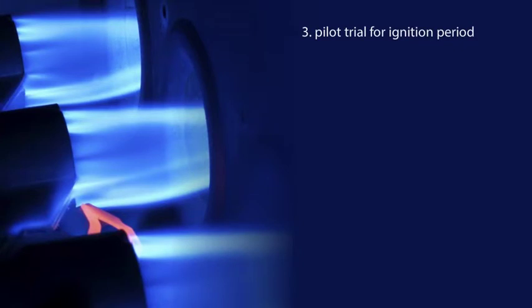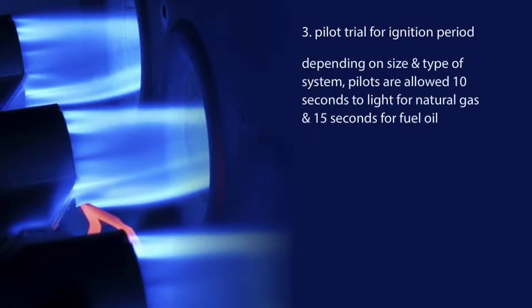The pilot trial for ignition period. Depending on the size and type of system, pilots are allowed 10 seconds to light for natural gas and 15 seconds for fuel oil. This is often a configurable setting on modern BMSs, although in the case of some equipment, it's a permanent change. You can always decrease it, but you cannot increase it when configuring on most BMS systems. It should also be noted that some European codes allow only 4 seconds.